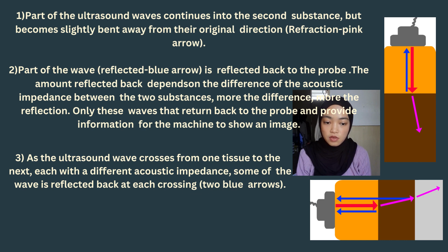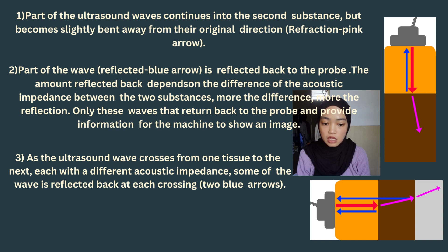The red arrow is the ultrasound wave. Part of the ultrasound wave continues into the second substance but becomes slightly bent away from the original direction. Look at the pink arrow. It bent. Part of the wave, the blue arrow, is reflected back to the probe. The amount reflected back depends on the difference of the acoustic impedance between the two substances. The more the difference, the more the reflection. Only this wave can return back to the probe and provide information for the machine to show the image. As the ultrasound wave crosses from one tissue to the next, each with different acoustic impedance, some of the wave is reflected back at each crossing. Look at the two blue arrows.